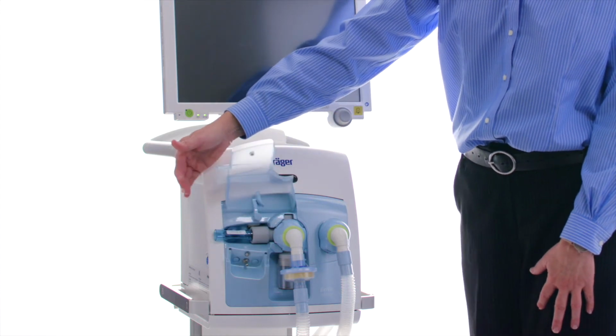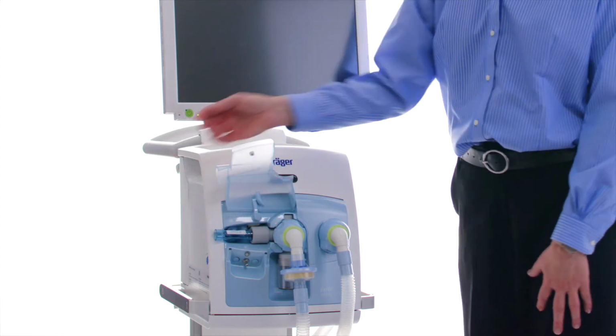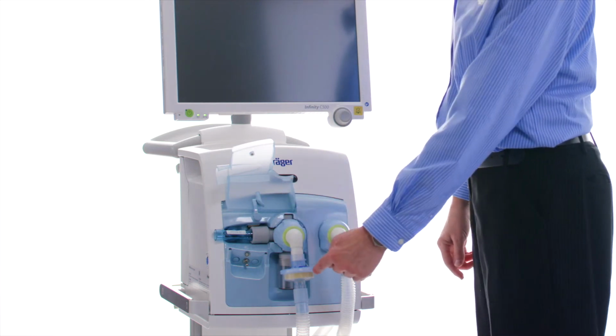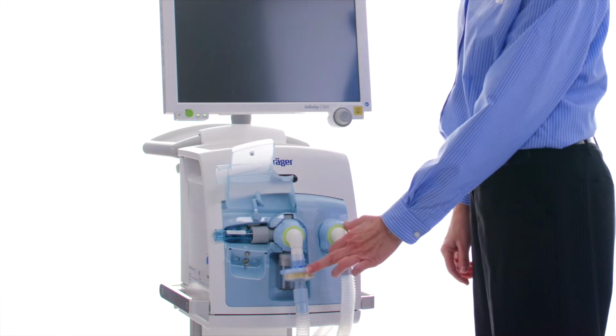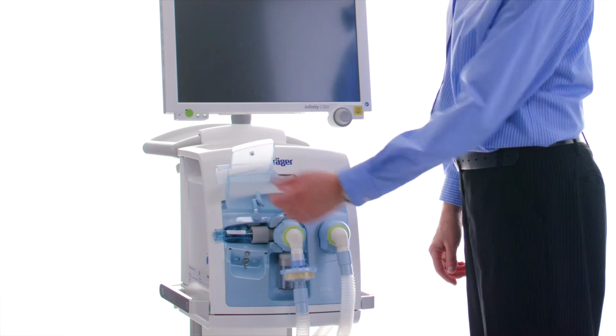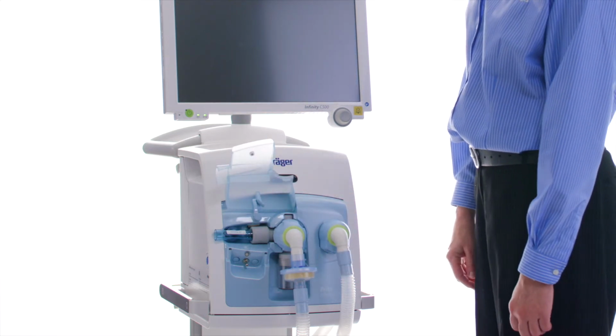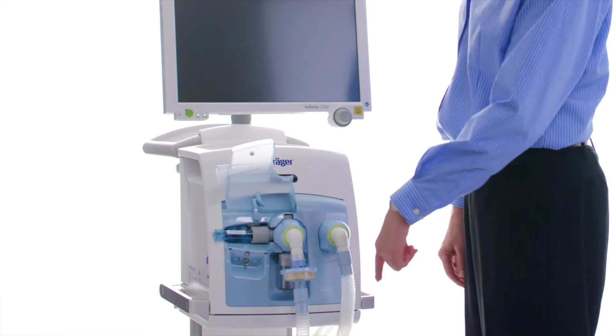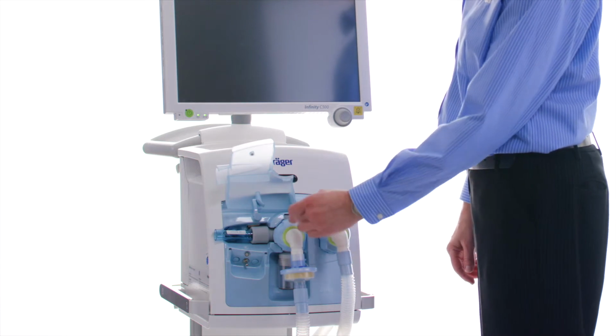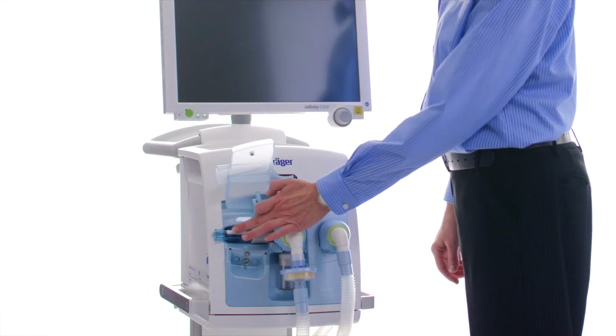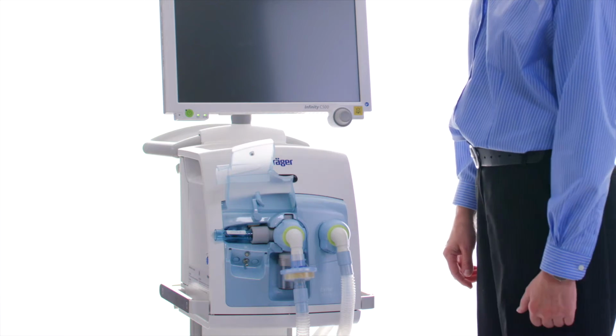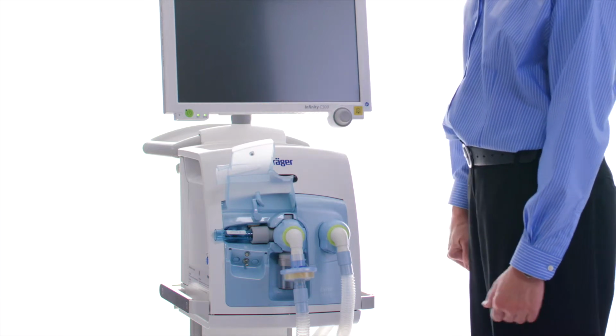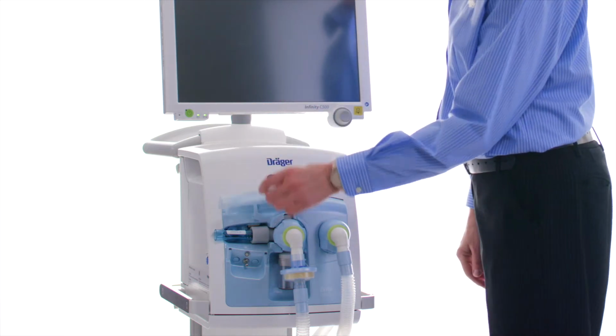If I open the door, I'm then going to find my flow sensor, and on the expiratory side of the circuit is where you would attach a filter should you want to filter the expired gas that goes to the environment. It's important to note that the gas flow goes through the expiratory valve, out the flow sensor, and gas never enters the box. There's no contaminated gas ever entering the machine.